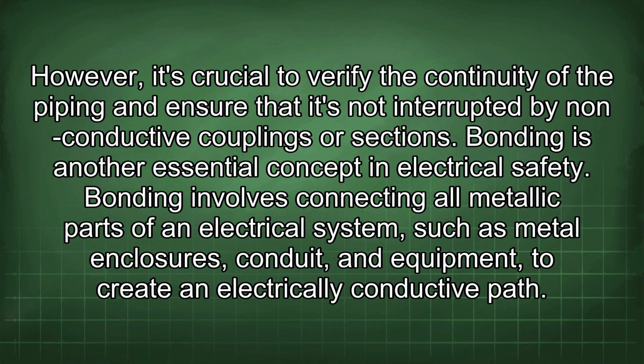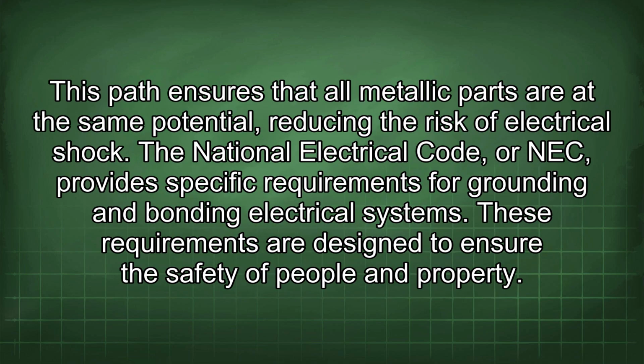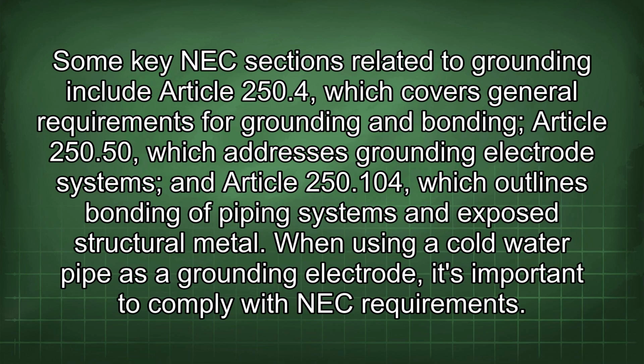non-conductive couplings or sections. Bonding is another essential concept in electrical safety. Bonding involves connecting all metallic parts of an electrical system, such as metal enclosures, conduit, and equipment, to create an electrically conductive path. This path ensures that all metallic parts are at the same potential, reducing the risk of electrical shock. The National Electrical Code, or NEC, provides specific requirements for grounding and bonding electrical systems. These requirements are designed to ensure the safety of people and property. Some key NEC sections related to grounding include Article 250.4, which covers general requirements for grounding and bonding, Article 250.50, which addresses grounding electrode systems, and Article 250.104, which outlines bonding of piping systems and exposed structural metal.